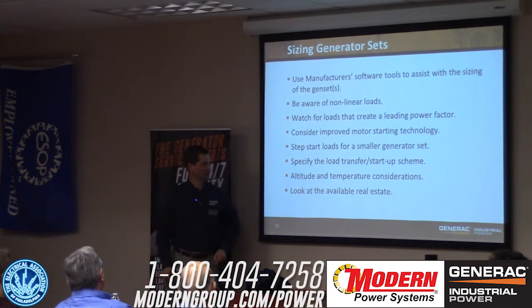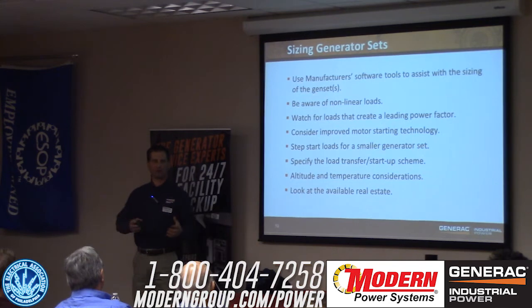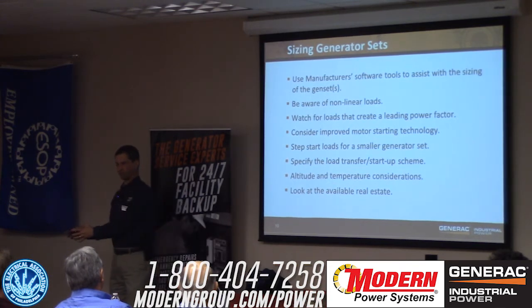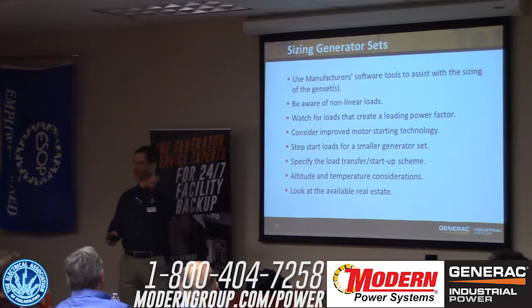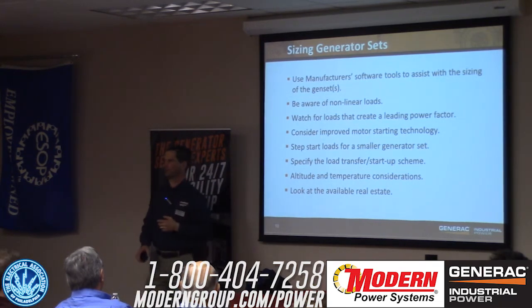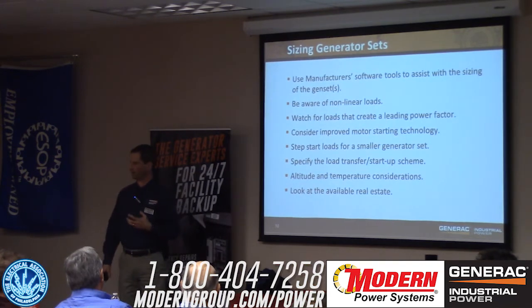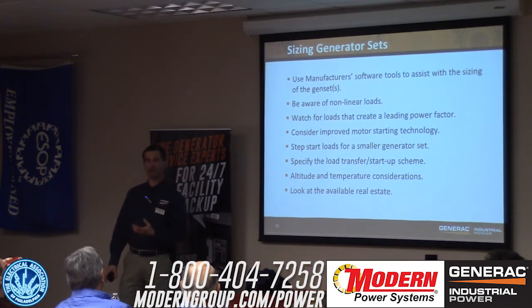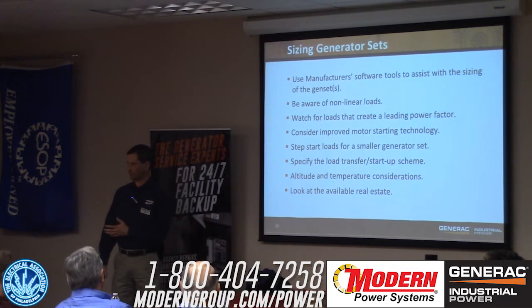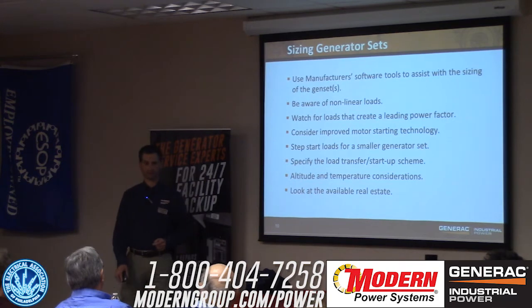We'll want to specify the load, the transfer startup scheme. Do they want the lights to go out, right? Are we going to transfer to a neutral position, let motors spin down, and then roll over to our generator? Depending on your loads, that might be the way to go. Or do I have a very generic office environment? I don't really have anything special in there. The idea is to minimize that outage. Maybe I use an in-phase transfer switch, which can roll from the utility over to the generator very, very quickly, and then similarly from the gen set back to the utility with almost no break.